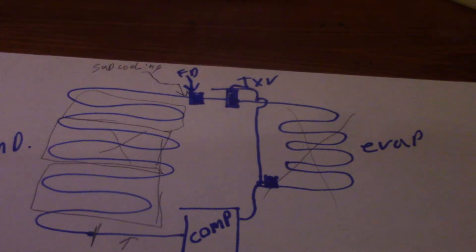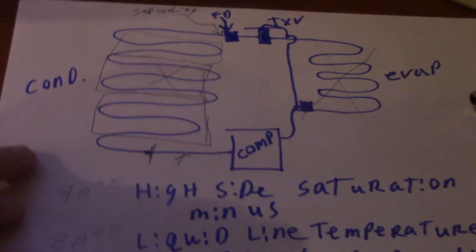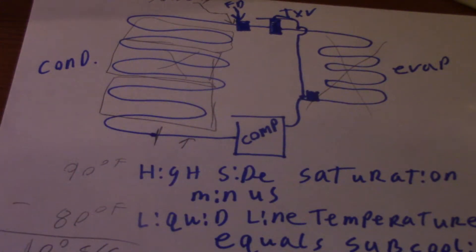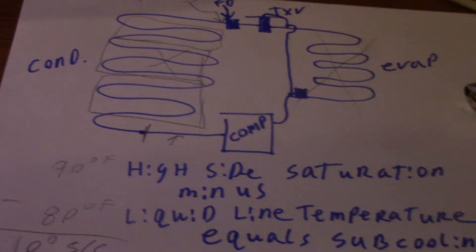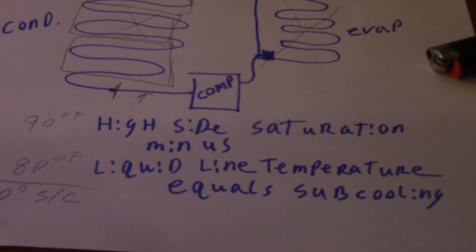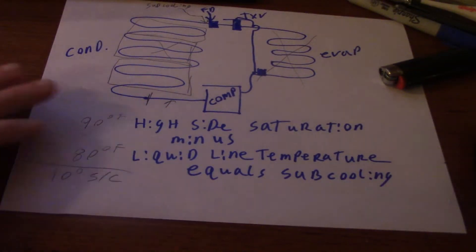If you don't follow the formula that we have stated there, high side saturation minus liquid line, and try to do, say, a big number minus little number deal, well, you'll calculate the wrong information.